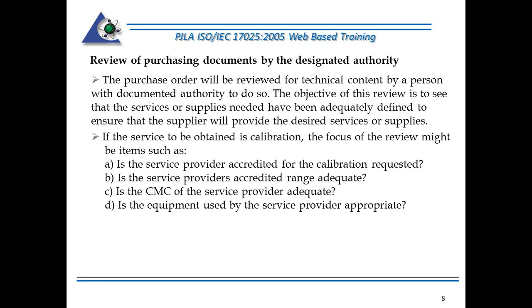If several of them could satisfy your accuracy requirement and had CMCs low enough to be acceptable, then you would probably pick the one that you would use based on how soon the calibration could be performed if time was critical. But you would perhaps eliminate several and keep several and pick from the remaining ones based on either price or availability of services and supplies.